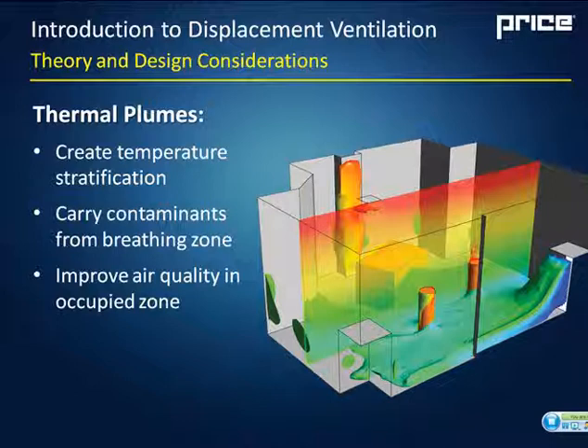What that obviously does is improves the air quality in the occupied zone. If you remember back to the mixing case, we would have a diffuser in the ceiling that would be mixing all of that air back down into the occupied zone. So anything that someone is breathing on one side of the room is basically going to be mixed back down into the occupied zone to someone on the other side of the room.